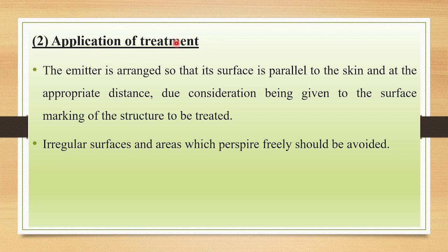So next is application of treatment. The emitter is arranged so that its surface is parallel to the skin at an appropriate distance, due consideration being given to the surface marking of the structure to be treated. Irregular surfaces and areas which perspire freely should be avoided.